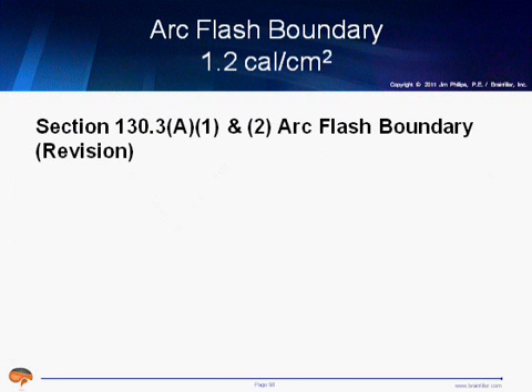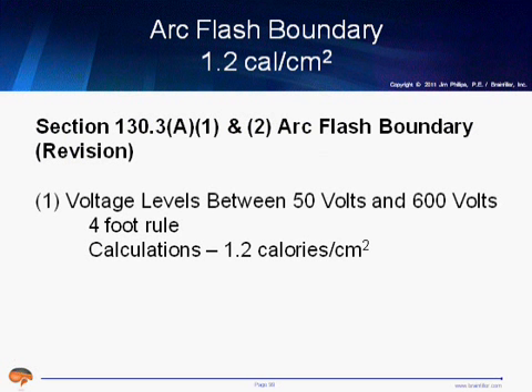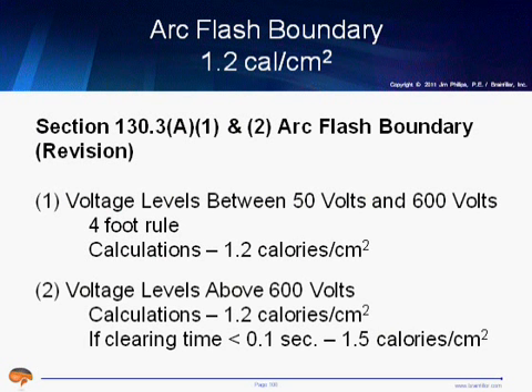Some other changes. The arc flash boundary, this was back in the 2009 edition. There were a couple of ways to go about this. For systems between 50 and 600 volts, we had the 4-foot rule, which is going away. Otherwise, you calculate the arc flash boundary based on the distance at which the energy drops to 1.2 calories per square centimeter. That's the threshold of a second-degree burn. For voltages above 600 volts, 1.2 calories was used unless the clearing time is less than a tenth of a second. In that case, you were permitted to define the boundary as 1.5 calories per square centimeter.